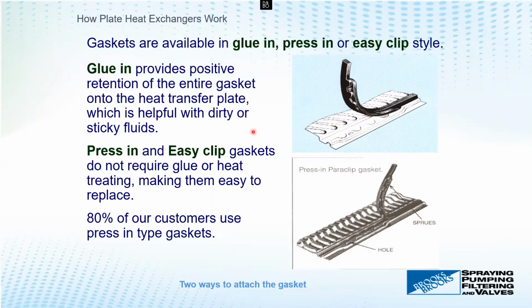Over time, pretty much every manufacturer has come up with a system to press in or clip in gaskets. Instead of gluing and curing, they now have little sprues on their gaskets and some alignment tool, whether it's in the edge of the gasket, the edge of the gasket groove, or some kind of hole in the groove—this whole groove is non-wetted, everything's inside in the flow path. The sprues align with where they're supposed to go in the gasket groove, and away you go—you press the gaskets in the whole way around. Labor savings is tremendous, and it's easy to maintain since they stay in the groove just fine.